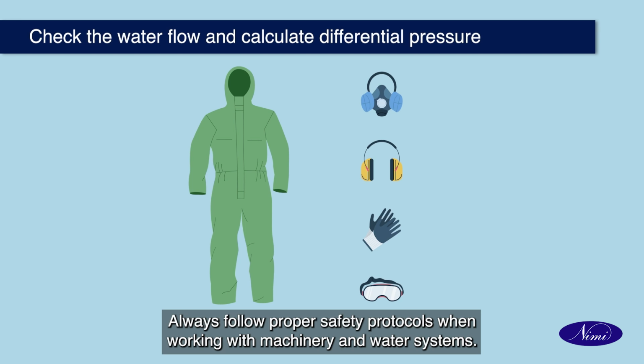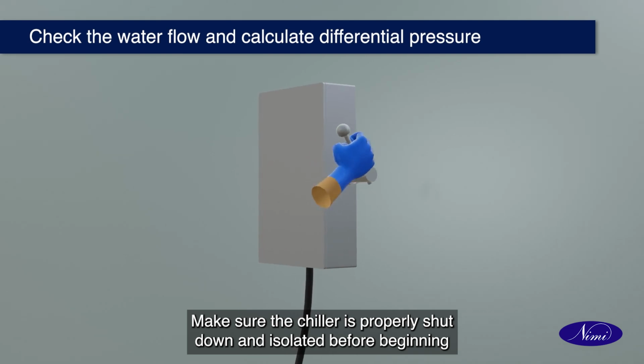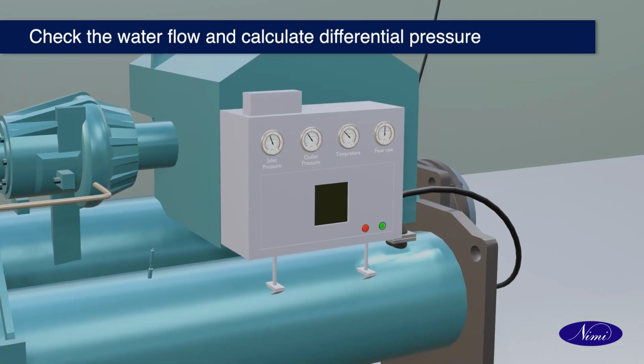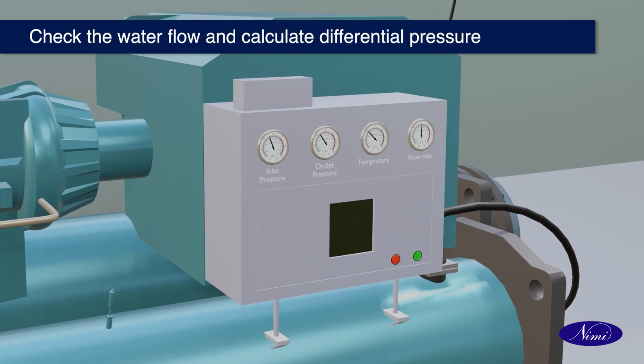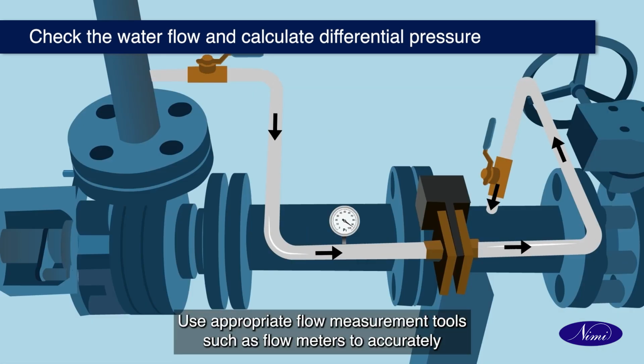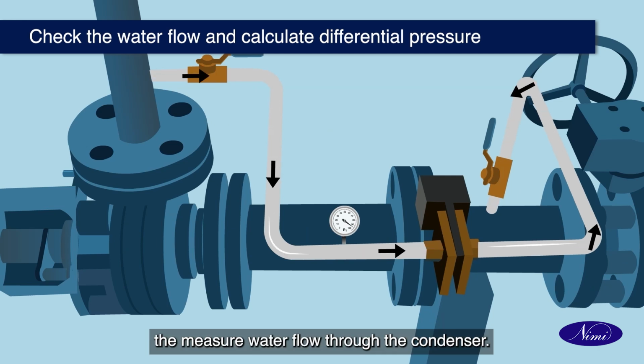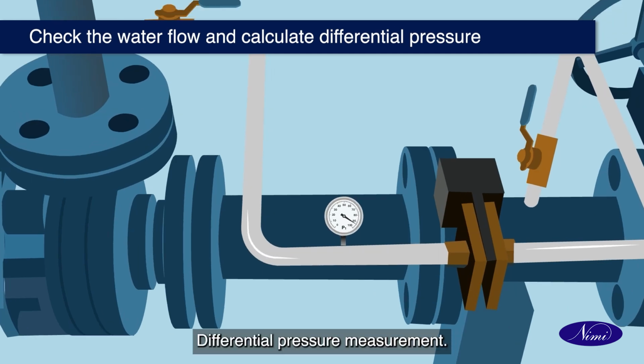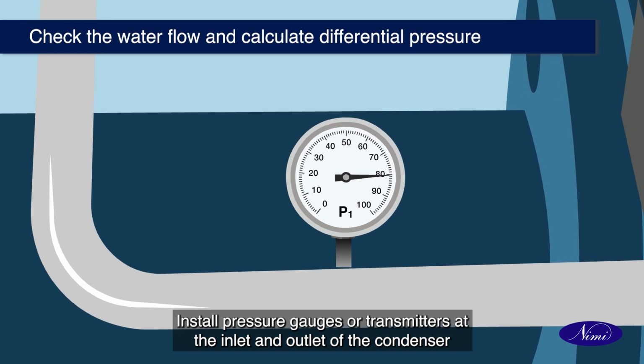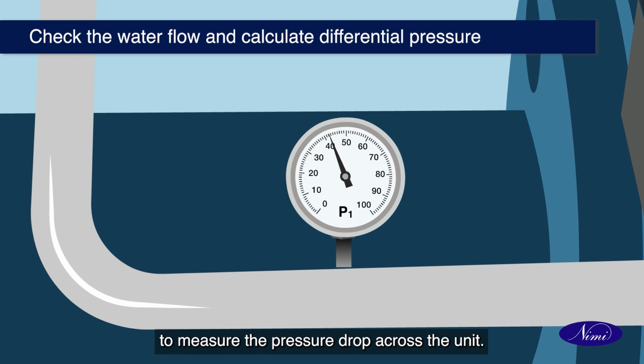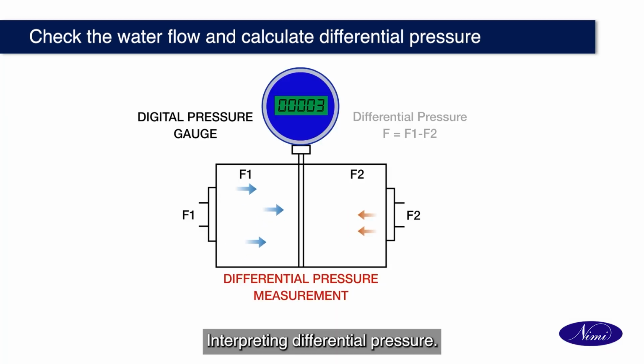Safety first. Always follow proper safety protocols when working with machinery and water systems. Make sure the chiller is properly shut down and isolated before beginning any inspection or maintenance. Flow measurement. Use appropriate flow measurement tools such as flow meters to accurately measure water flow through the condenser. Differential pressure measurement. Install pressure gauges or transmitters at the inlet and outlet of the condenser to measure the pressure drop across the unit.